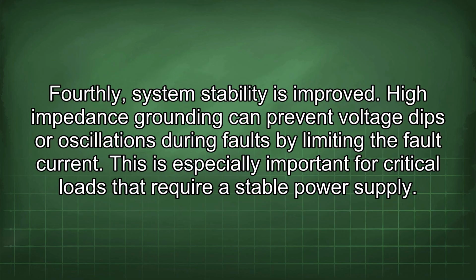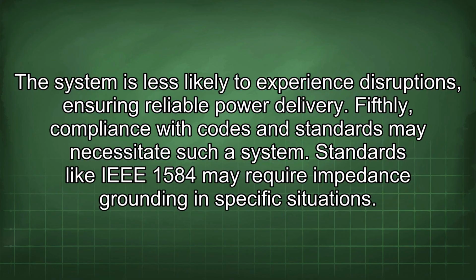Fourthly, system stability is improved. High impedance grounding can prevent voltage dips or oscillations during faults by limiting the fault current. This is especially important for critical loads that require a stable power supply. The system is less likely to experience disruptions, ensuring reliable power delivery.